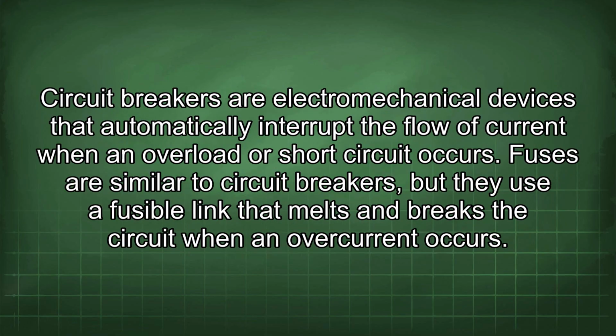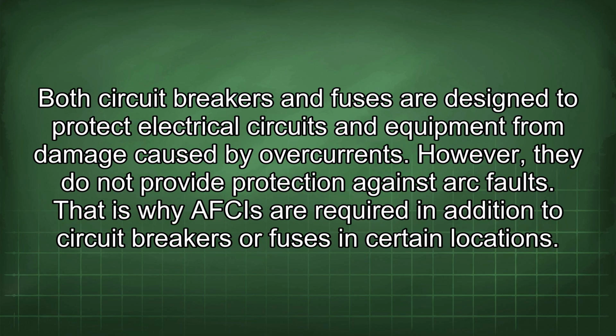Circuit breakers are electromechanical devices that automatically interrupt the flow of current when an overload or short circuit occurs. Fuses are similar to circuit breakers, but they use a fusible link that melts and breaks the circuit when an overcurrent occurs. Both circuit breakers and fuses are designed to protect electrical circuits and equipment from damage caused by overcurrents. However, they do not provide protection against arc faults. That is why AFCIs are required in addition to circuit breakers or fuses in certain locations.